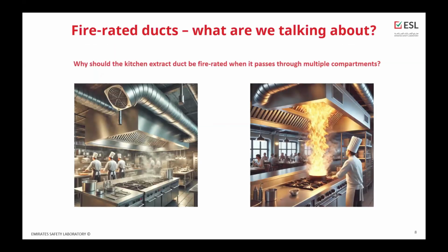The next very important aspect of fire safety related to ducts is kitchen extraction ducts, which are installed in commercially operated kitchens across the globe, in all restaurants. Discussing fire safety in the building, we just cannot omit these ducts in commercial use, especially since some regions are still using ducts which are not fire rated or are made of materials which are not appropriate for this use, like aluminium duct. So what are the threats coming from this situation, especially when the duct is passing through several compartments? What can happen if non-fire-rated ducts are used in these commercial kitchens?